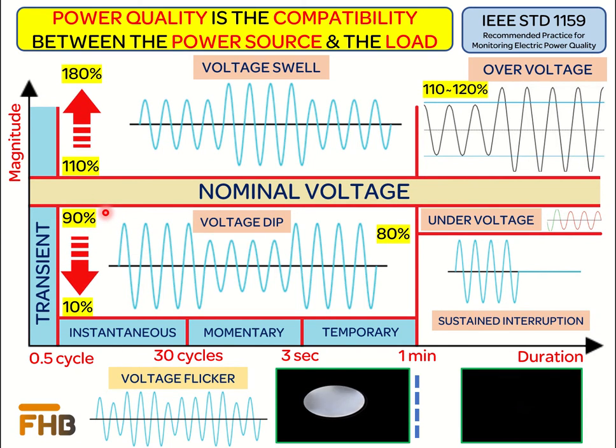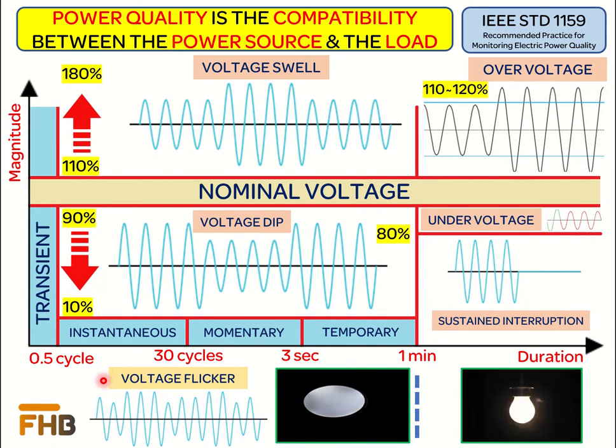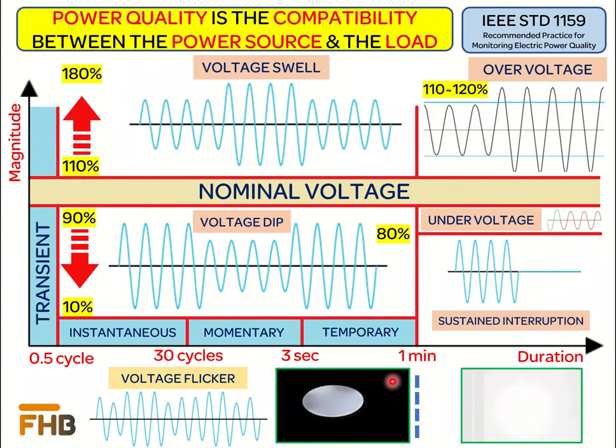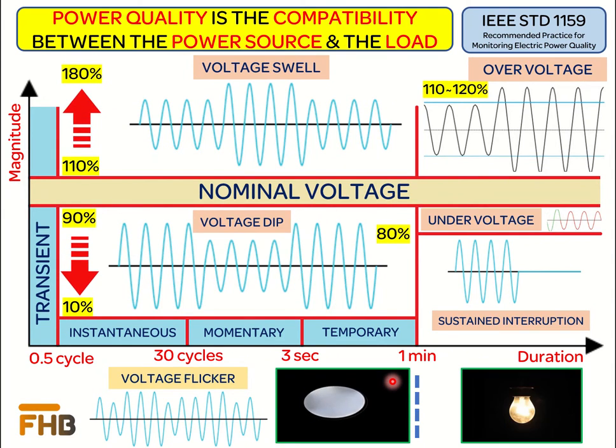Typical magnitude of voltage sag ranges from 90% to 10% of the nominal voltage. Voltage flicker or voltage fluctuation is limited to lighting applications and is mostly considered as a nuisance. This effect is produced due to systematic variation in the voltage waveform. As per IEEE standard, any variation in the voltage magnitude which is less than 7% of the nominal voltage has little effect on other types of consumer loads.